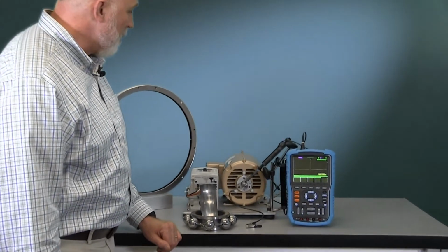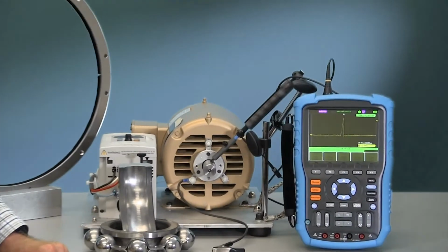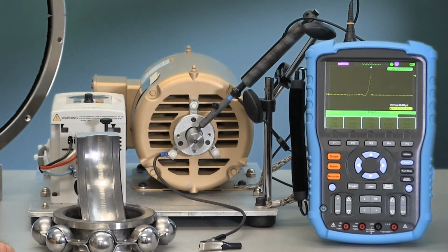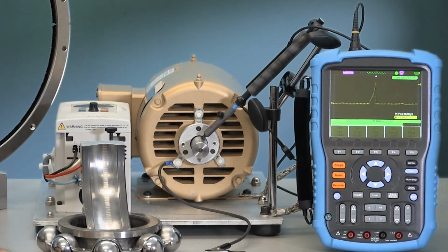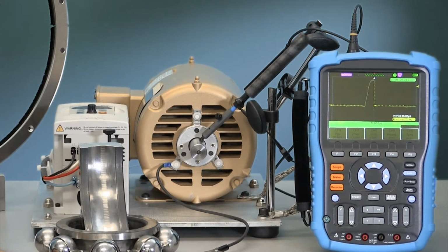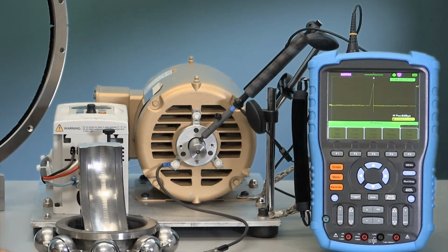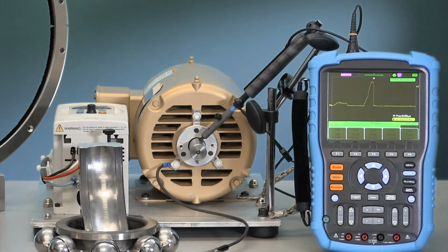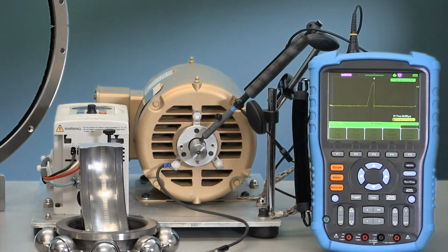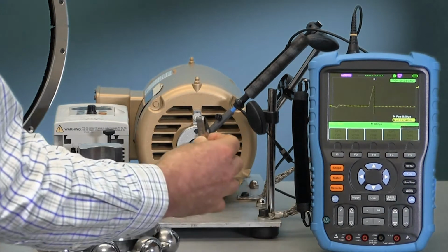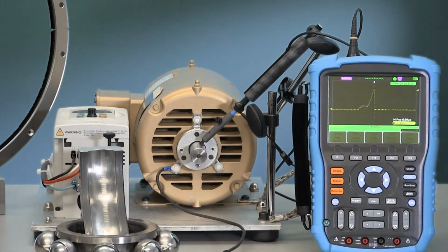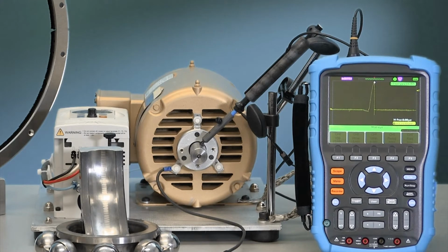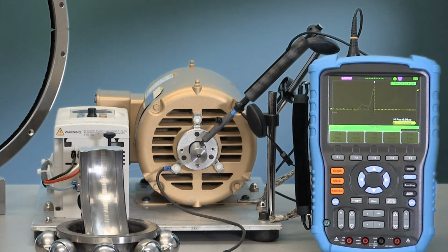So in this setup, we have a motor operated by the VFD, and you can see the shaft voltage tester and the shaft voltage probe, which is touching the motor shaft. That allows us to measure if there's any voltage on the shaft surface. In addition, you see that this motor has a shaft grounding ring installed, but it's installed with nylon plastic screws, so it's not currently connected to ground. We would actually have to connect this ring to ground in order to protect the motor from bearing damage.